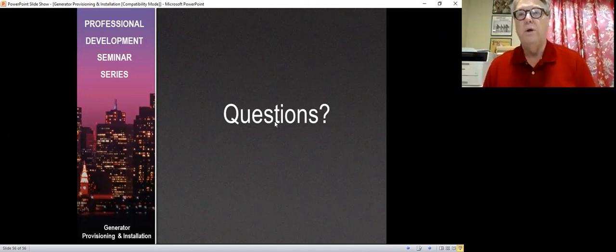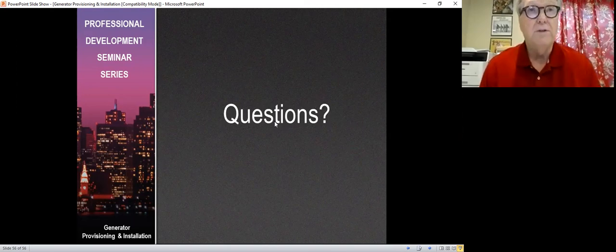And so what you need to do is a level 2 enclosure. Like I say, I'm a big fan of that because a level 2 enclosure is typically the quietest enclosure that you can get without costing an arm and a leg. And you can stand right next to a level 2 enclosure generally and have a conversation. So I recommend level 2, and sometimes that's all you need to spec. But if you really want to know what the dBA level is, you have to ask for a certain dBA level. And I would call a generator manufacturer before I do that.